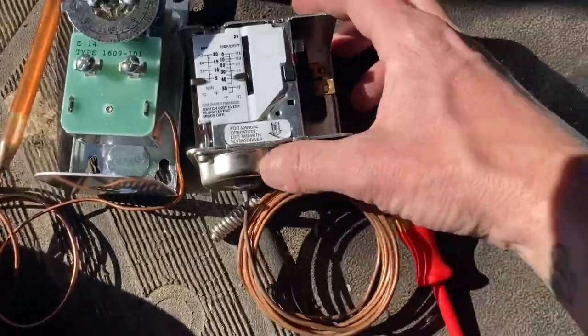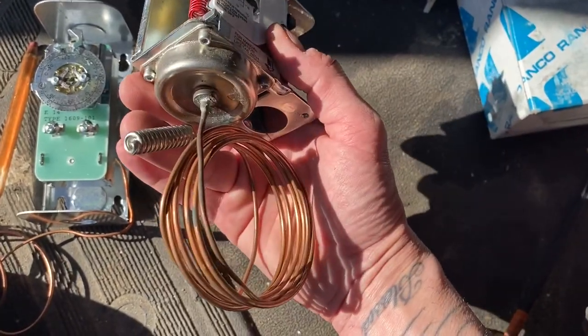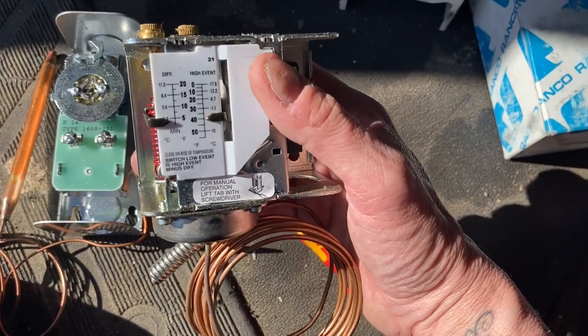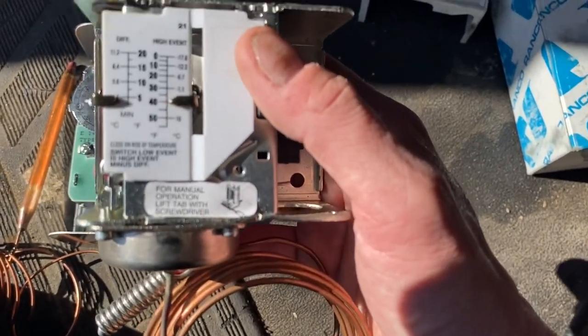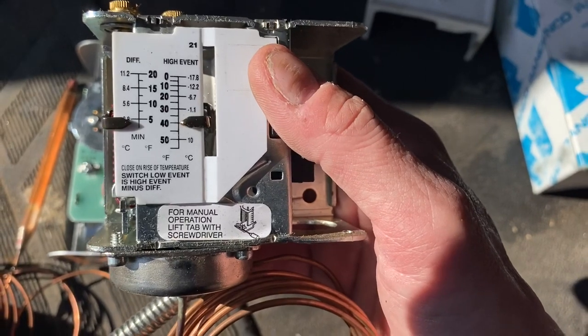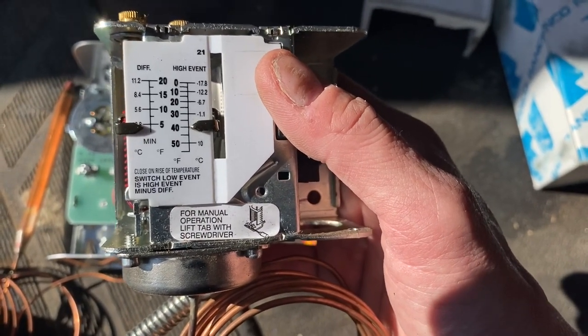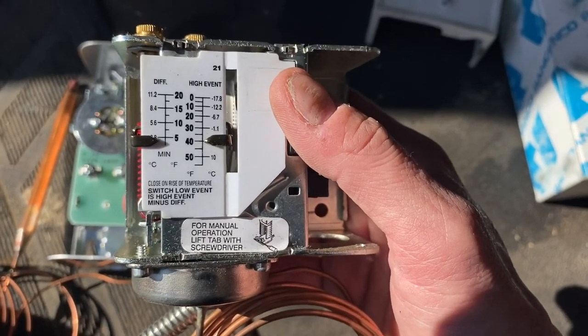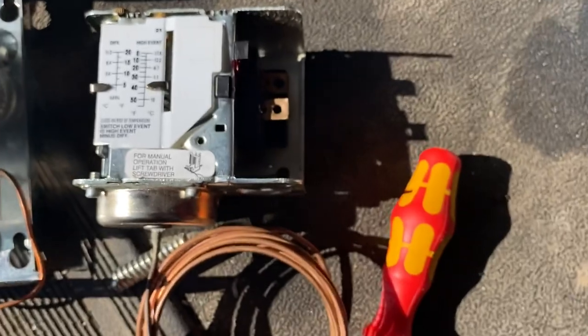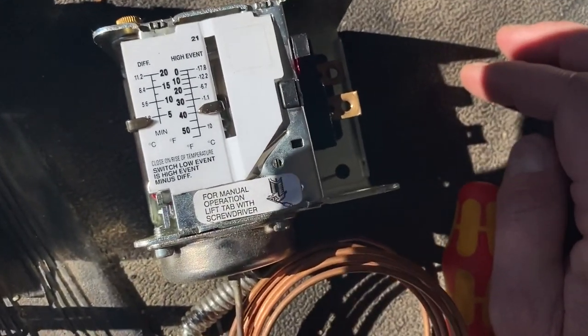This one here looks like a pressure control, so you have to make sure it's your temperature control — you can see it has a different probe on it, but they all look the same. This one has two different adjustments: your high event, which is your temperature, set at about 40 right now, and your differential, which is set at about 3. That means when the temperature in your box rises to 40 degrees or so, this is going to come on.